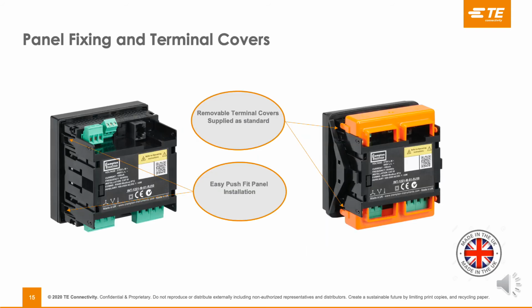As we mentioned on the previous slides, the product comes as standard with the orange terminal covers, which relates to the colour of TE connectivity. These terminal covers are removable, so the product can be installed and wired and then the terminal covers clipped on afterwards. If you look to where the orange cover meets the black casing, on either side there are two little white holes where, if required, a tamper-proof seal can be fitted onto the meter, so that if anybody does break the seal, you know somebody has been into the product.